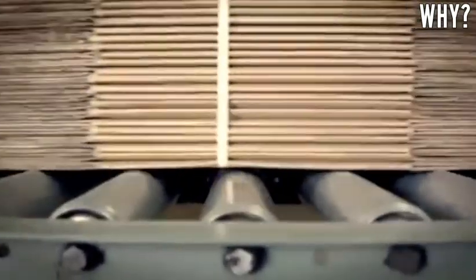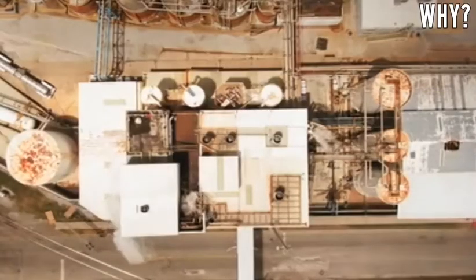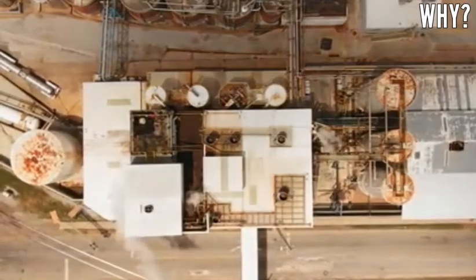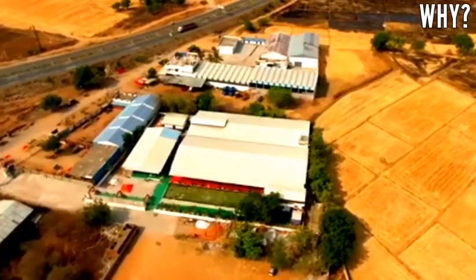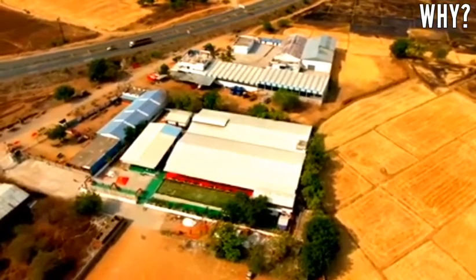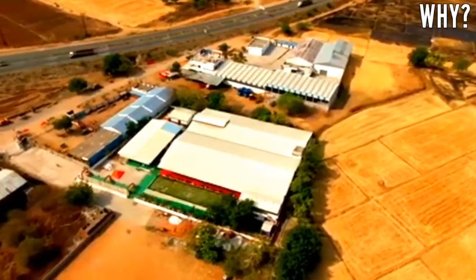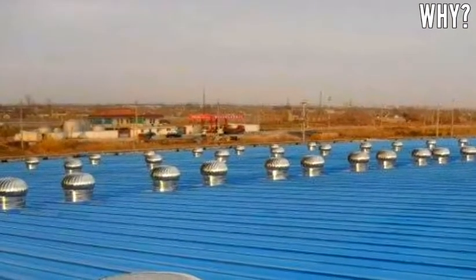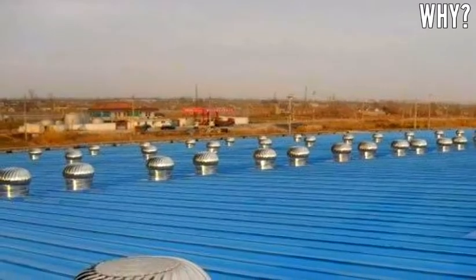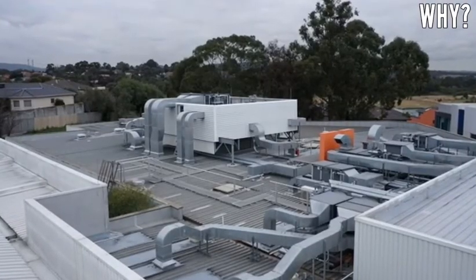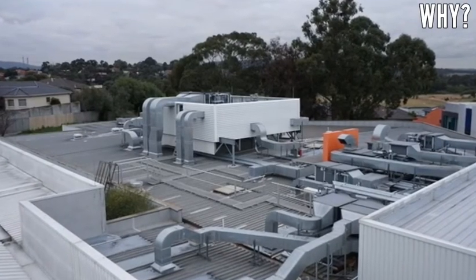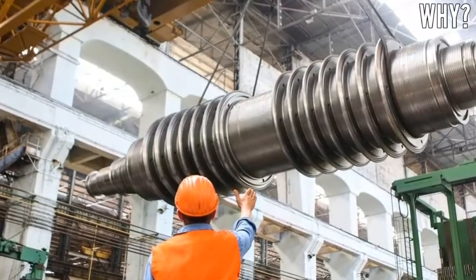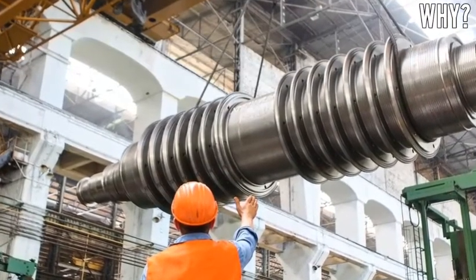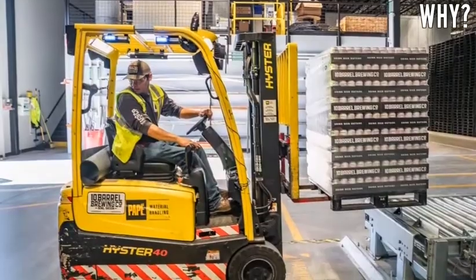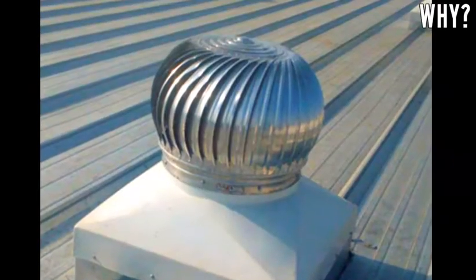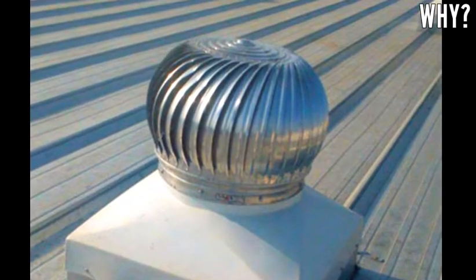Now, as you can see in this image, which is when the rooftop ventilators are provided, the hot air which is near the roof will find itself a way to escape to the atmosphere by rotating the rotor, which is located in the ventilator at the top of the roof. The breeze outside also has an effect in rotation of the rotor. This causes a reduction in pressure in that region and causes more air to escape through the ventilator, leading to an increase in ventilation of the building.